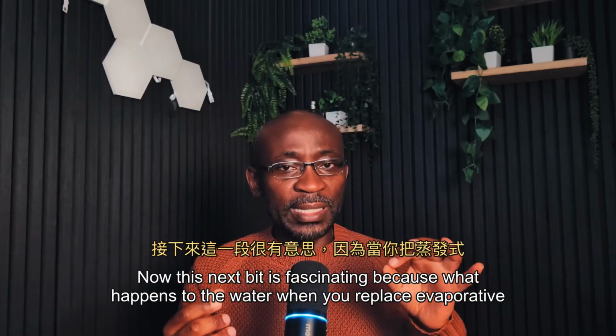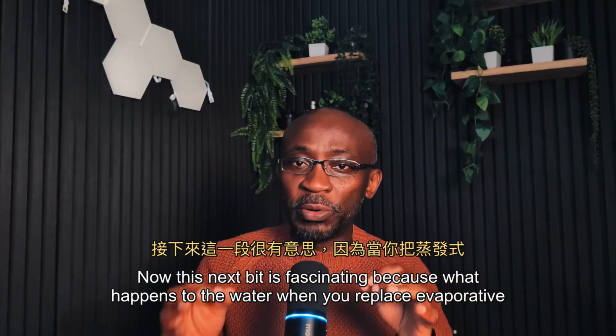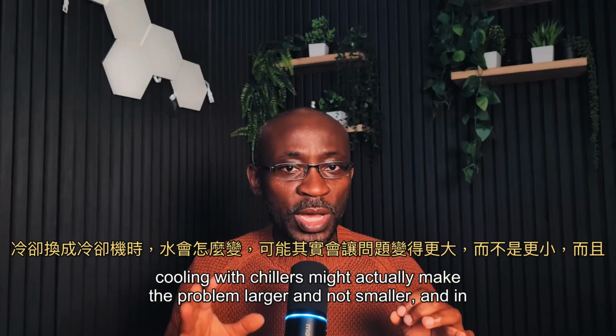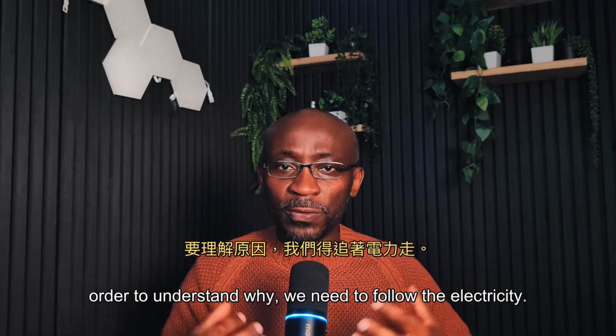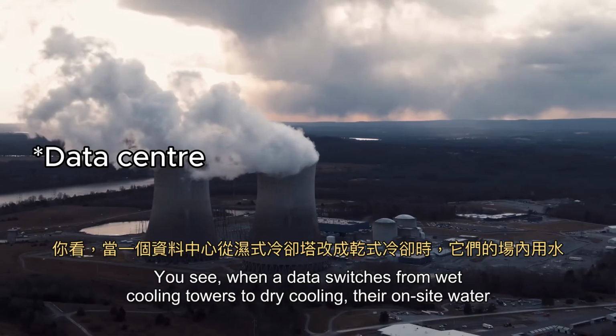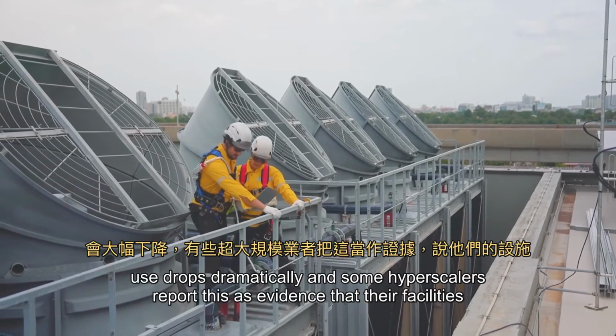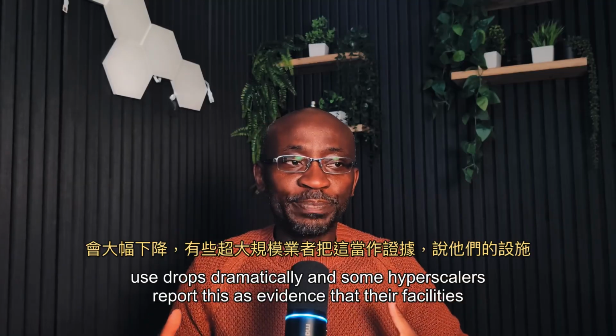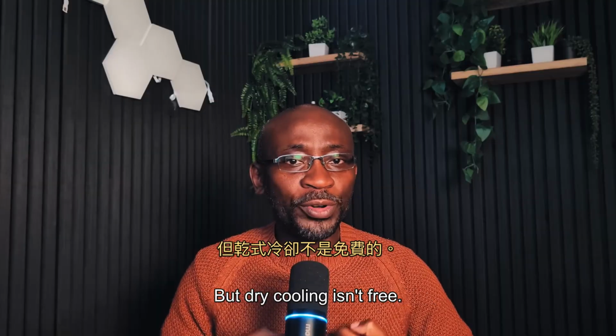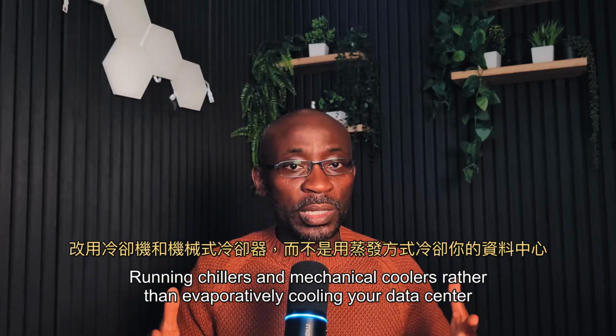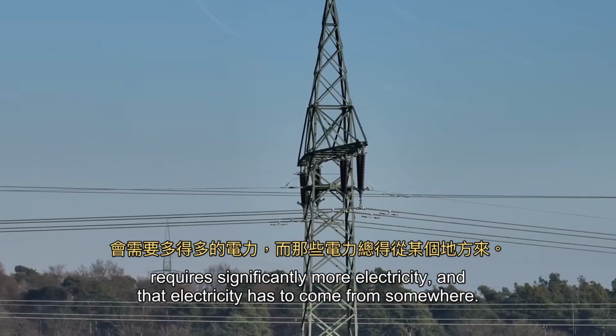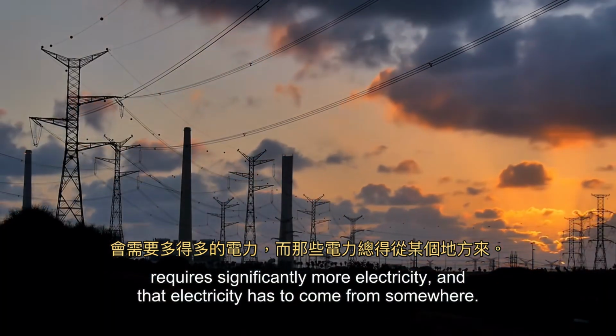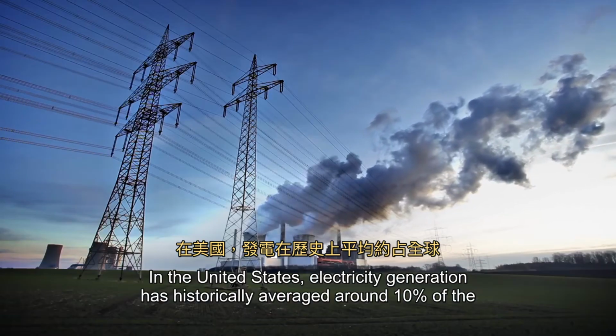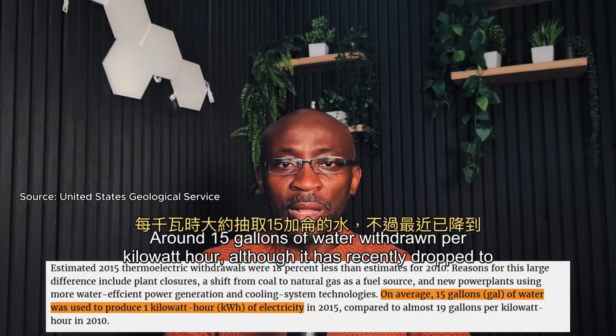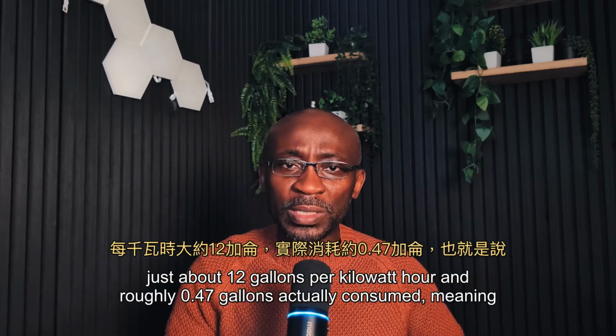And now, this next bit is fascinating because what happens to the water when you replace evaporative cooling with chillers might actually make the problem larger and not smaller. And in order to understand why, we need to follow the electricity. You see, when a data center switches from wet cooling towers to dry cooling, their on-site water use drops dramatically, and some hyperscalers report this as evidence that their facilities are becoming more sustainable. But dry cooling isn't free. Running chillers and mechanical coolers rather than evaporatively cooling your data center requires significantly more electricity, and that electricity has to come from somewhere. In the United States, electricity generation has historically averaged around 15 gallons of water withdrawn per kilowatt hour, although it has recently dropped to just about 12 gallons per kilowatt hour, and roughly 0.47 gallons actually consumed, meaning it doesn't return to the source.